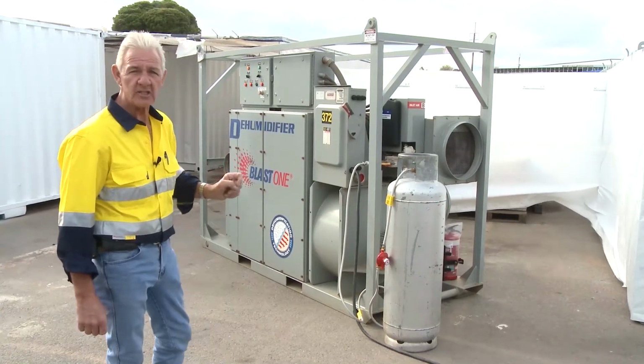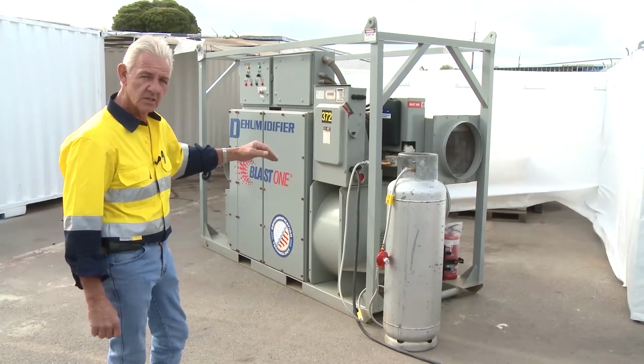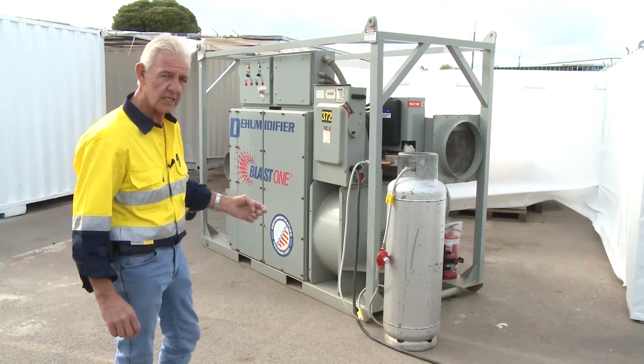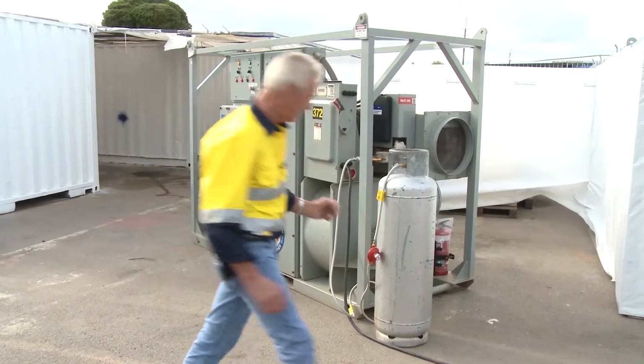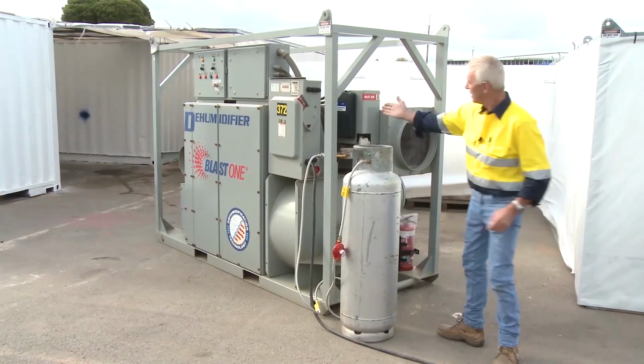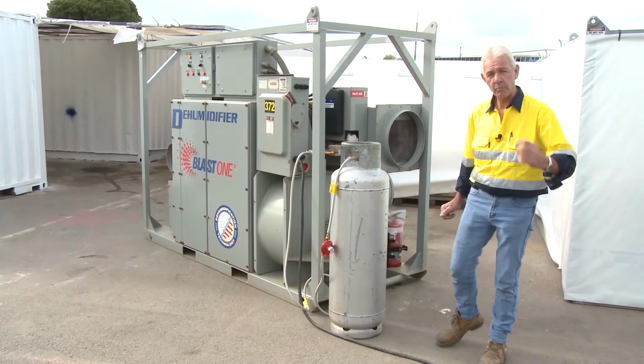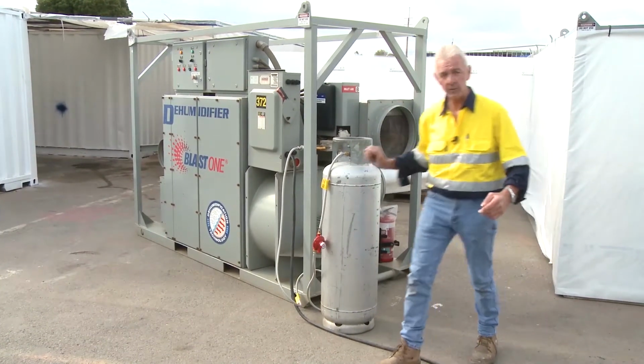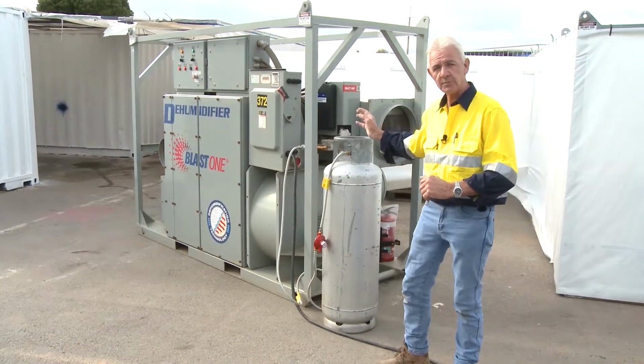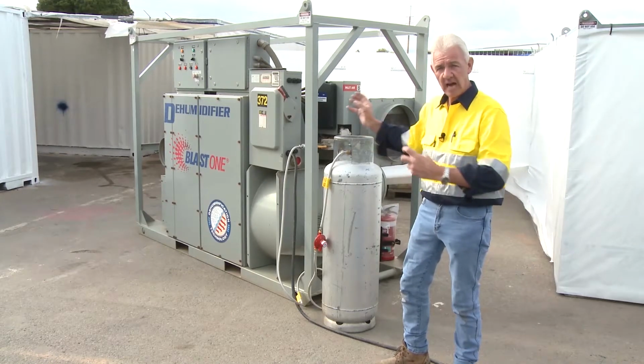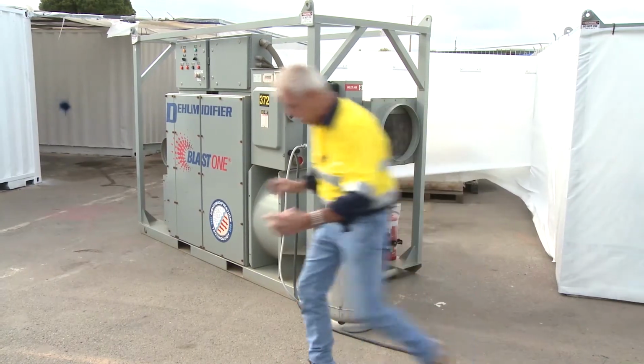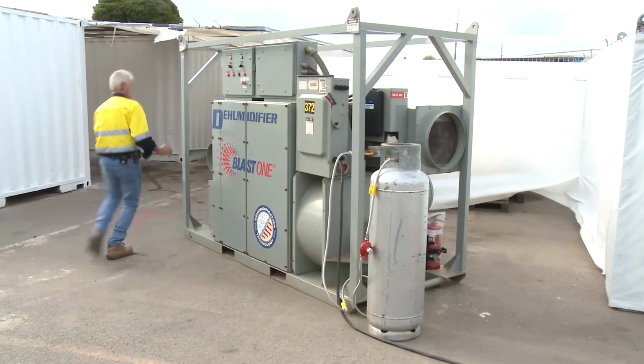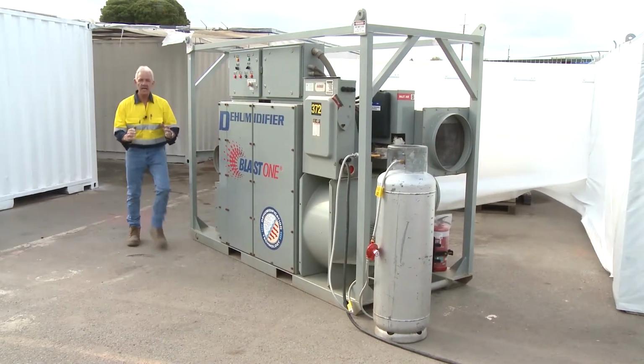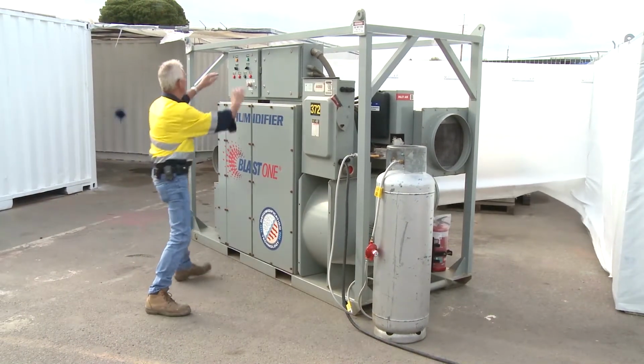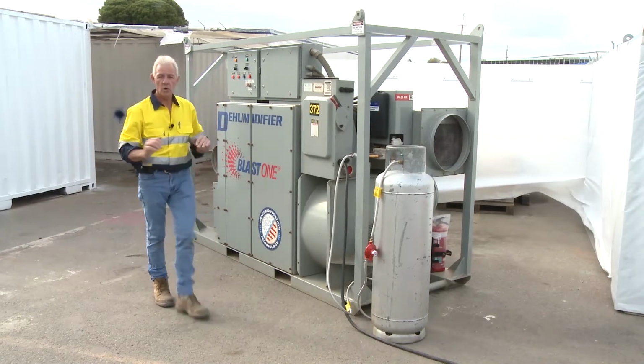So remember what I said about adjusting those butterfly valves to keep that air equal within the machine? A quick check to make sure that it's between 1 and 0.25, which is exactly where it is. So now I've checked that one. Just make sure its brother, the other side of it, is married to each other. So we'll go check that. So I've done those 2 checks. No lights illuminated. We're all good to go.